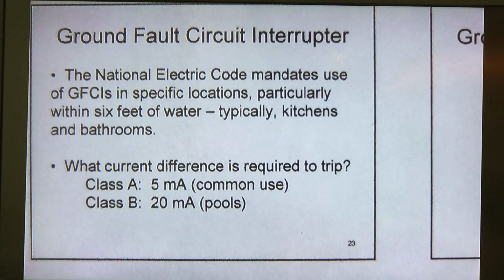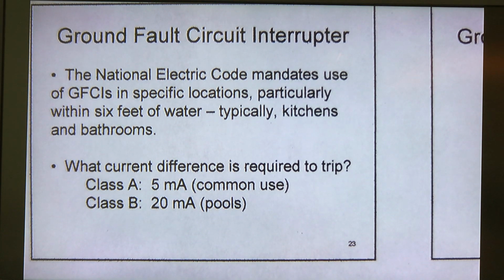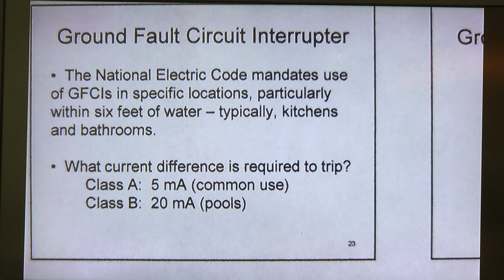The National Electric Code mandates the use of ground fault circuit interrupters as a protection device in specific locations, particularly within 6 feet of water. For example, kitchens, bathrooms are good examples. But they're useful in different parts of the house, but that's especially where they're used. You'll probably see them there if you see them anywhere. And the question comes up sometimes, what current difference is required to make it trip? In other words, how large a fault constitutes a ground fault? The most common is Class A GFCI, and that should trip at about 5 milliamperes. Pools are allowed a little bit more leeway at 20, but for the most part, you'll be dealing with a ground fault circuit interrupter that's a Class A device.